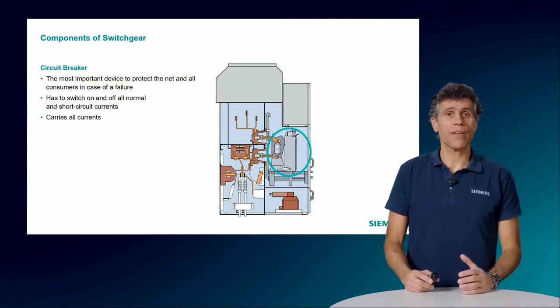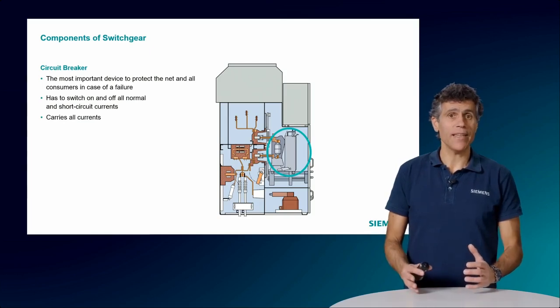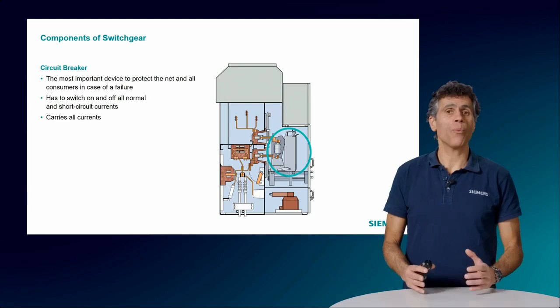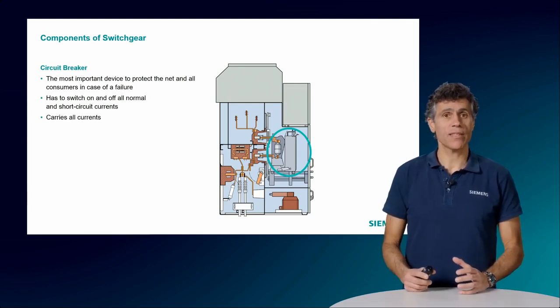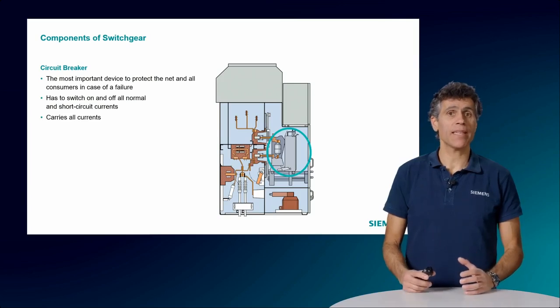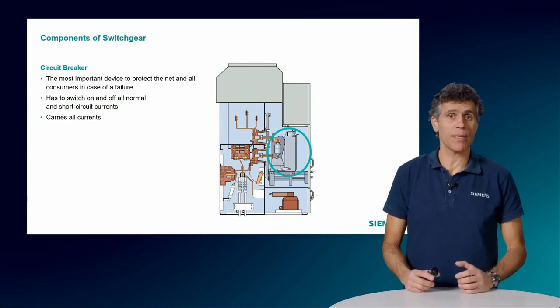Another different thing about the medium voltage circuit breaker is that in air-insulated switchgears they are often withdrawable. That means they can be removed from the voltage contacts while still inside the panel and can even be removed from the panel, for example for maintenance or replacement.